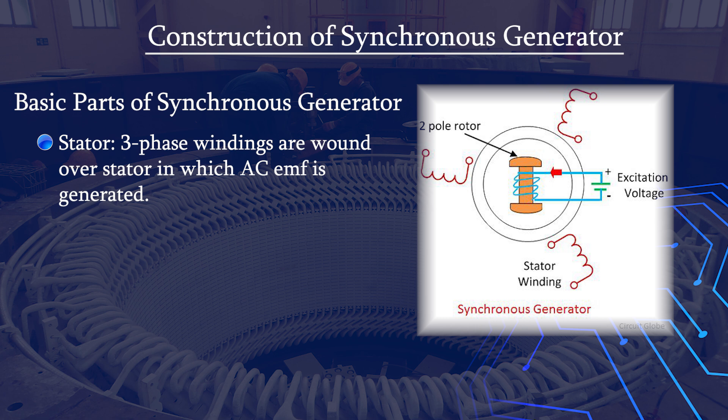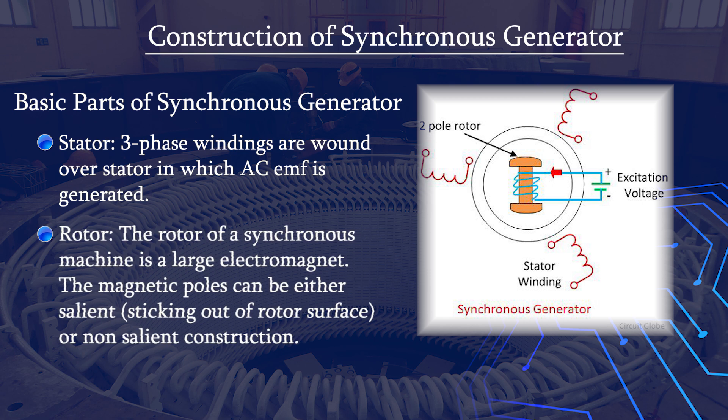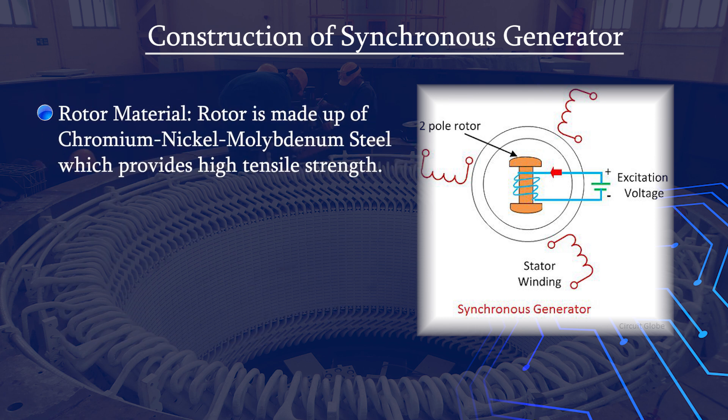The second component is the rotor. The rotor of a synchronous machine is a large electromagnet. The magnetic poles can be either salient, where the poles are projected out of the surface, or non-salient construction. The rotor material is chromium nickel molybdenum steel because it provides high tensile strength.